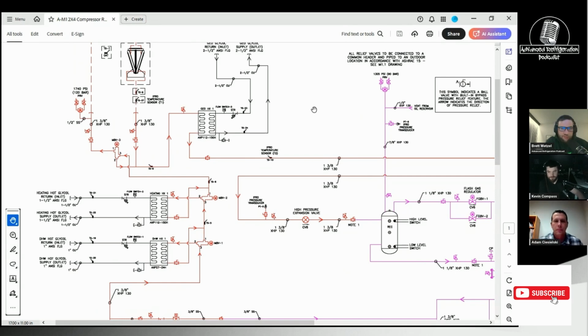So I have a question. You said before something about you were having a little bit of a hard time producing because the geo wells aren't heating up, aren't as hot as whatever. Is there anything that you could do as far as on the suction side, as far as floating some of the suction pressures a little bit higher, whether it be on the low temp or the medium temp, in order to get a little bit more capacity?